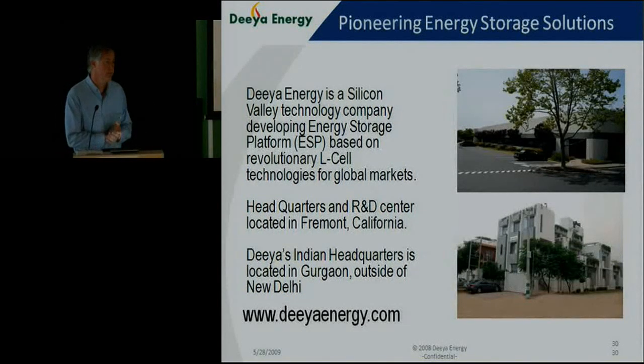And then you mentioned not needing to replace it, with a kind of 12-year lifespan. Yes. So how do you refresh the system? Good question. The question is, what will be needed to refresh the system after the end of life? Basically, what we see is that the cell stack needs to be replaced. We don't see much effect on the electrolyte. The pumps potentially might need to be replaced, but because the system is a machine, it's serviceable and can be restored by having new components put in the machine very easily.